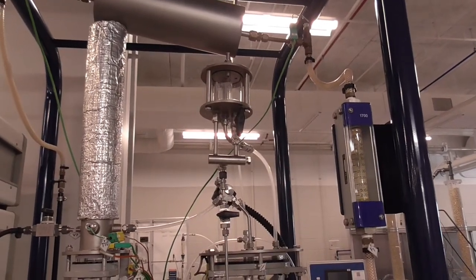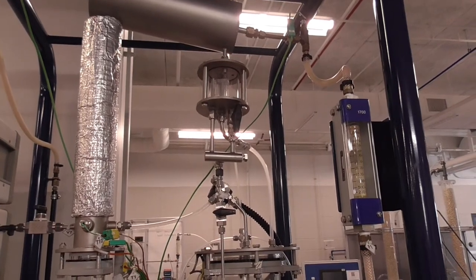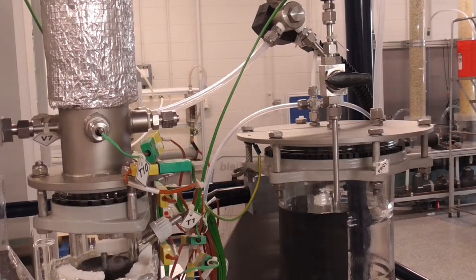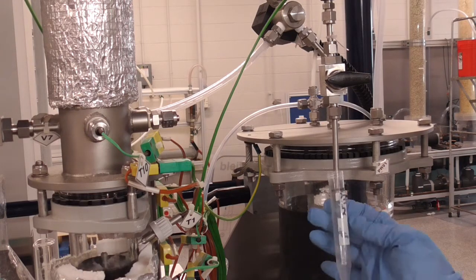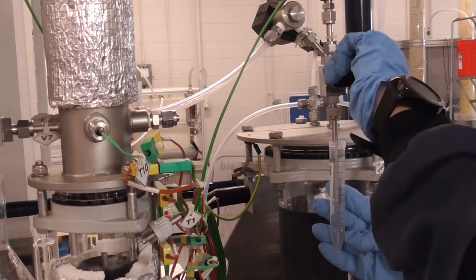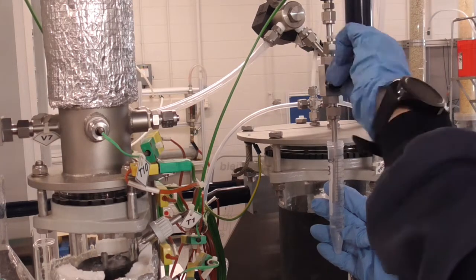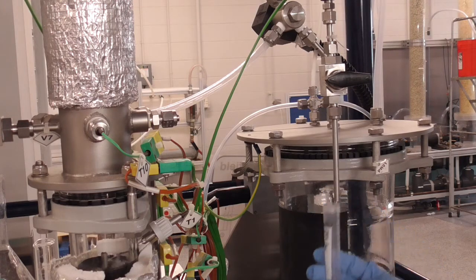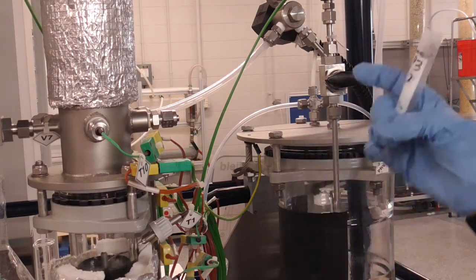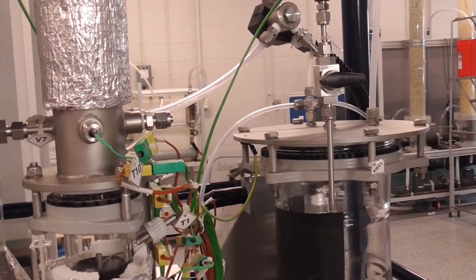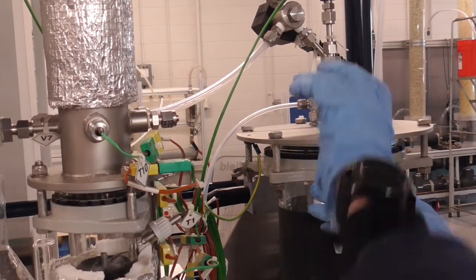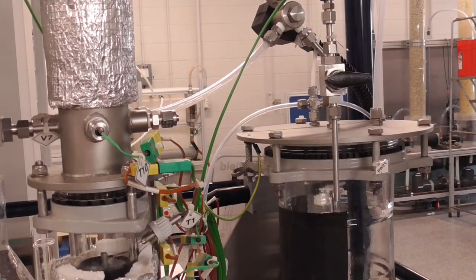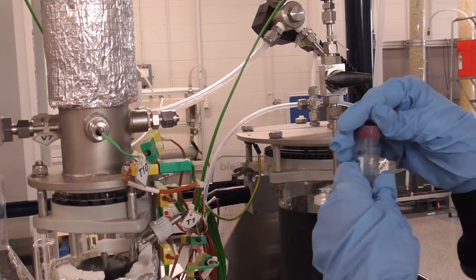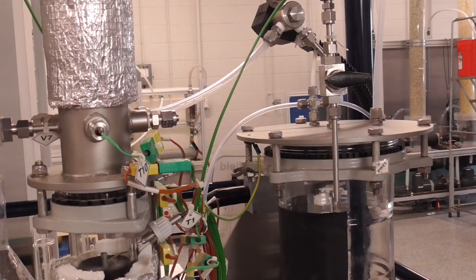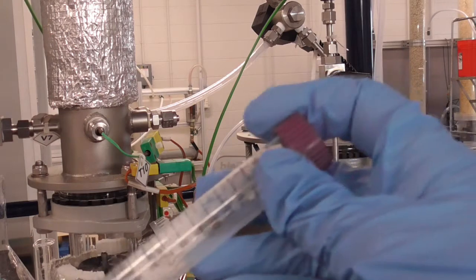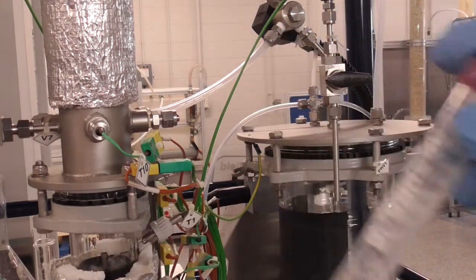The distillate will be sampled at V3 below the decanter. You can sample the distillate by putting the tube down inside the centrifuge tube and opening the valve V3. The first 5 milliliters is waste, and you're going to put it in the waste, and then you're going to get your sample and cap. Now this sample you want to put in the cooling bath to cool.